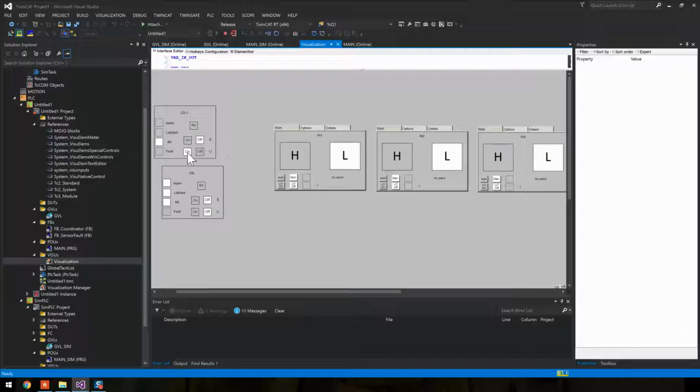So now it's automatically being suppressed, the low level sensor. The BX here, the input is true, so there is a fault detected, but there's no alarm, there's no latched alarm, nothing, because it's all suppressed. It is suppressed because there is a fault on the sensors.